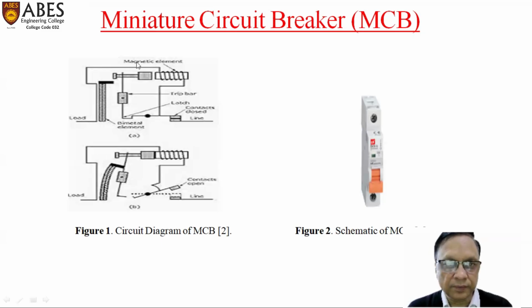Now let me tell you one thing. This is a latch. The trip bar is responsible; it is connected to the bimetal as well as to the magnetic material. In case of any fault, it will trip and open the contacts.